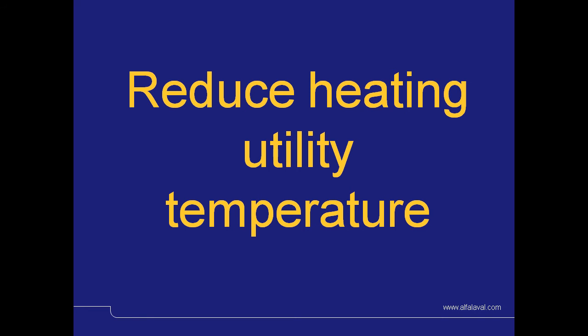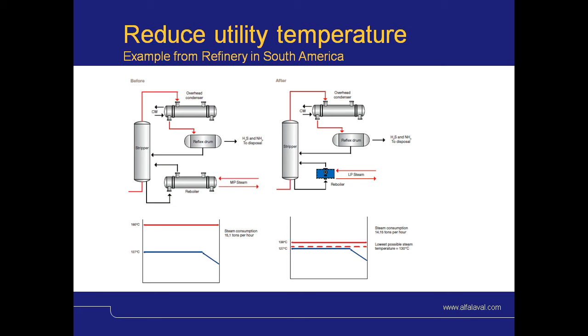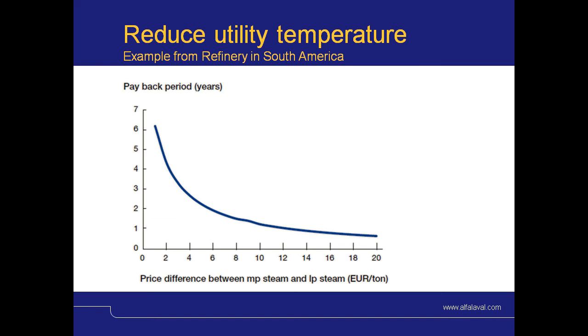Reduce heating utility temperature. This example shows the switch from a shell and tube reboiler using 180 degrees medium pressure steam to a compact heat exchanger reboiler that uses 138 degrees low pressure steam. Which is cheaper? The payback period is calculated on the price difference between the medium pressure steam and the low pressure steam.